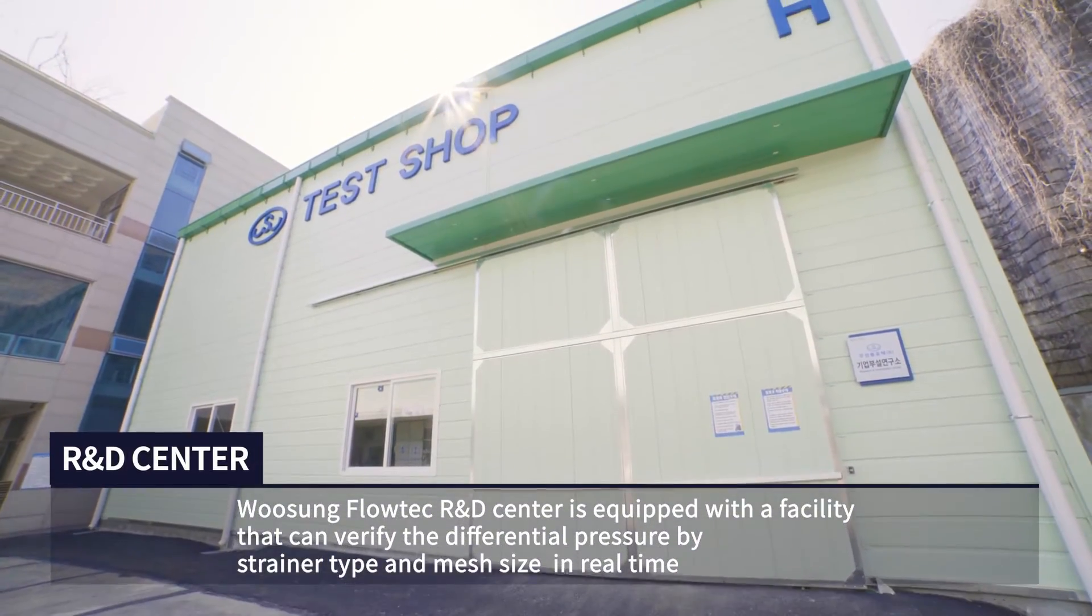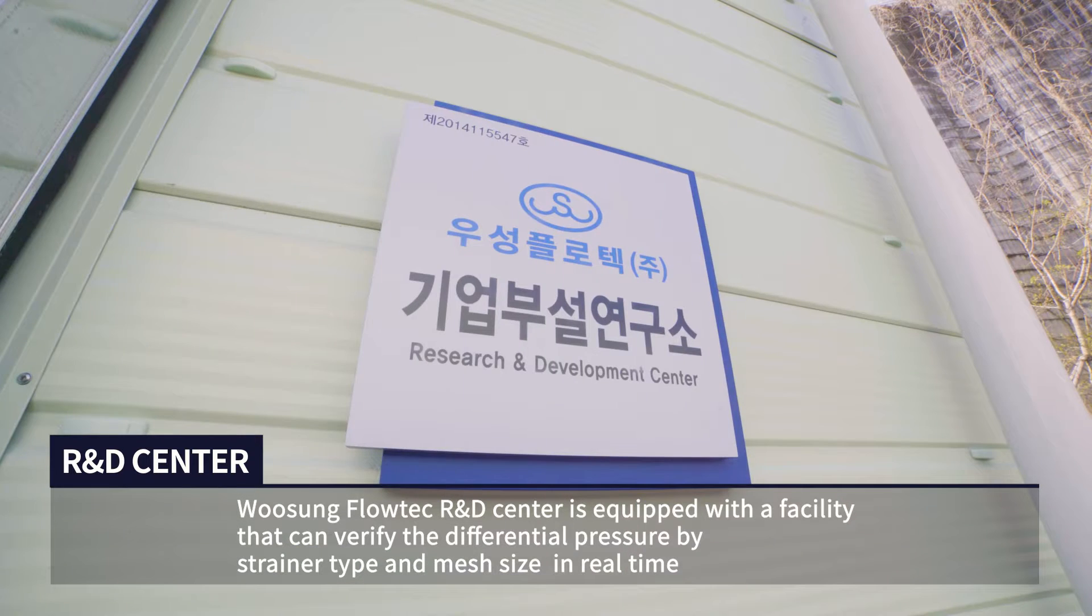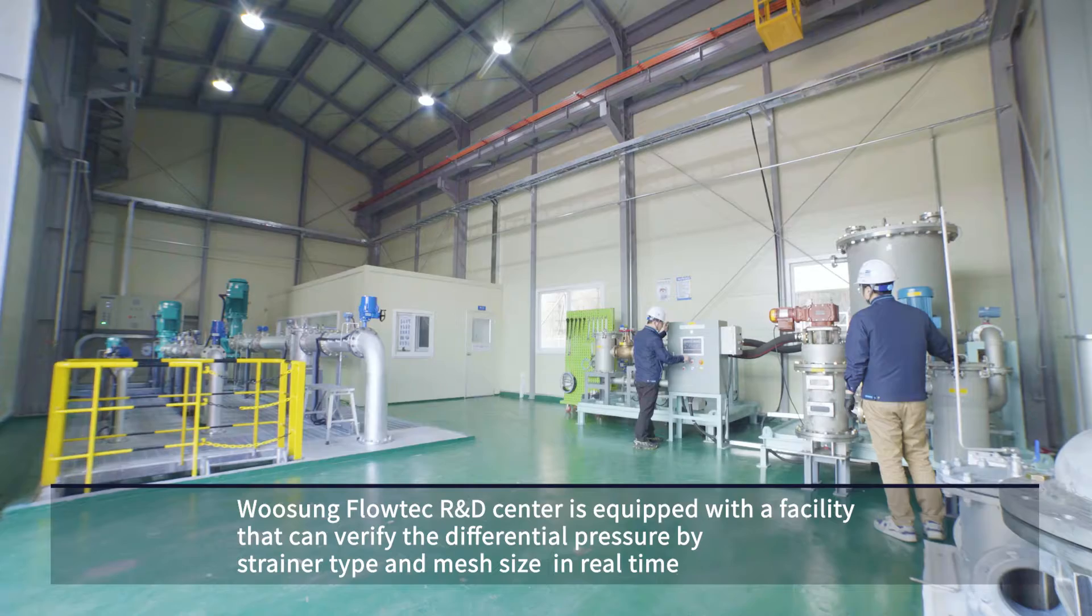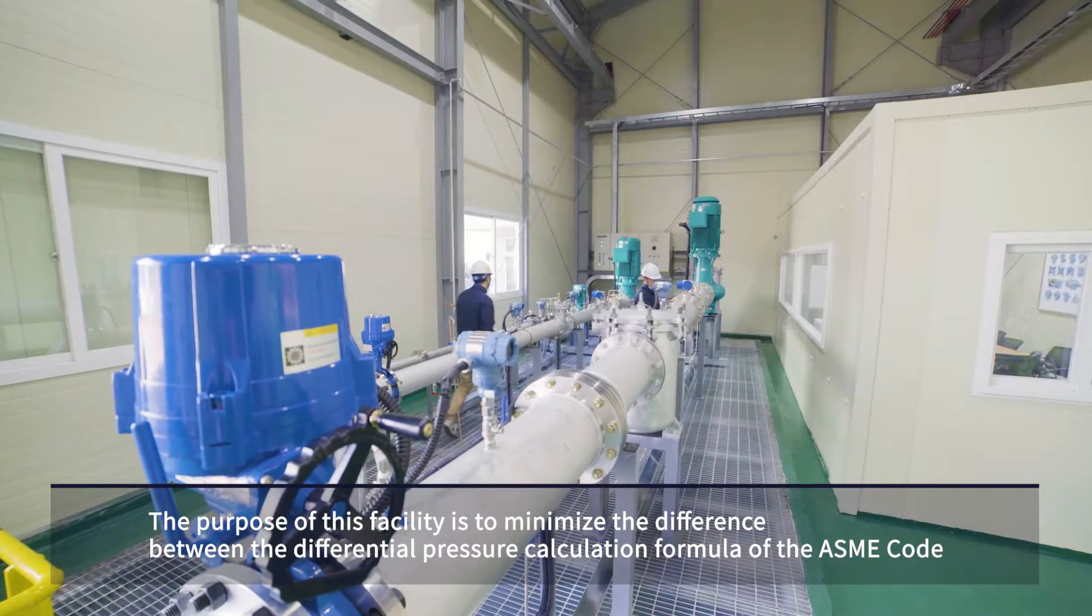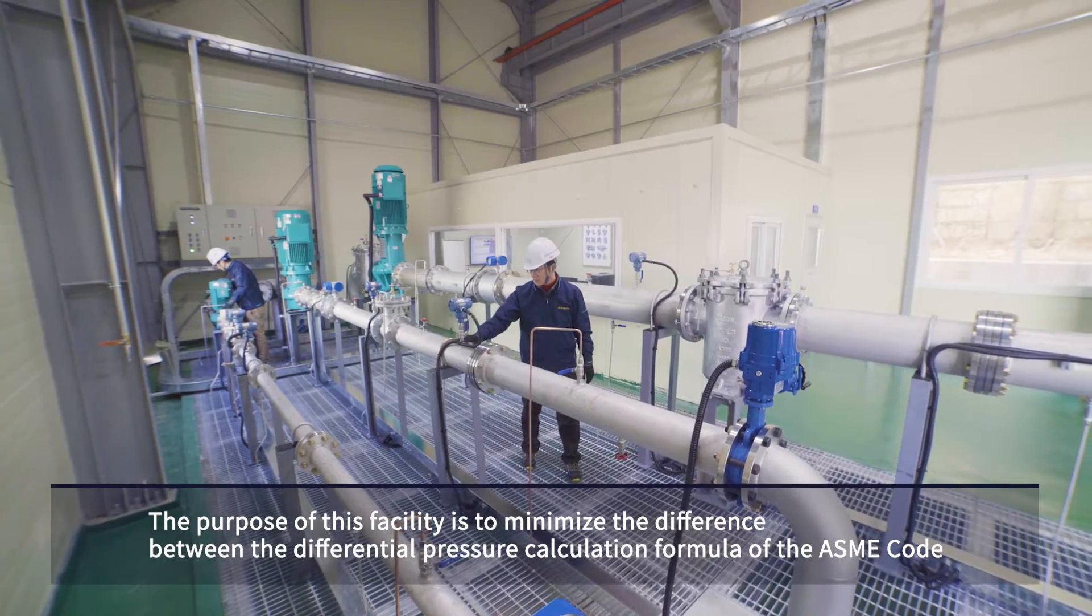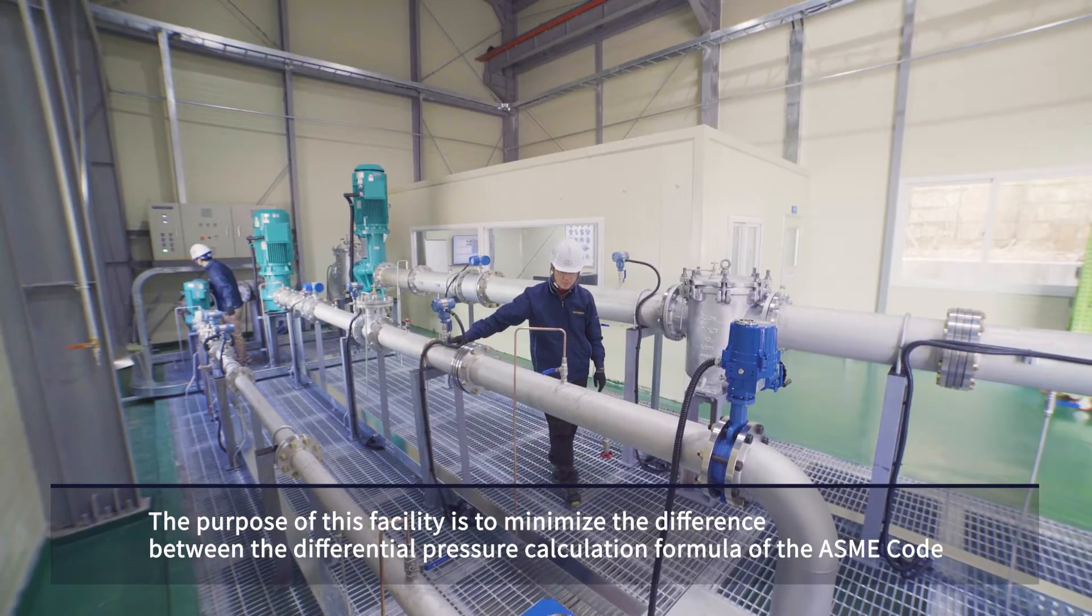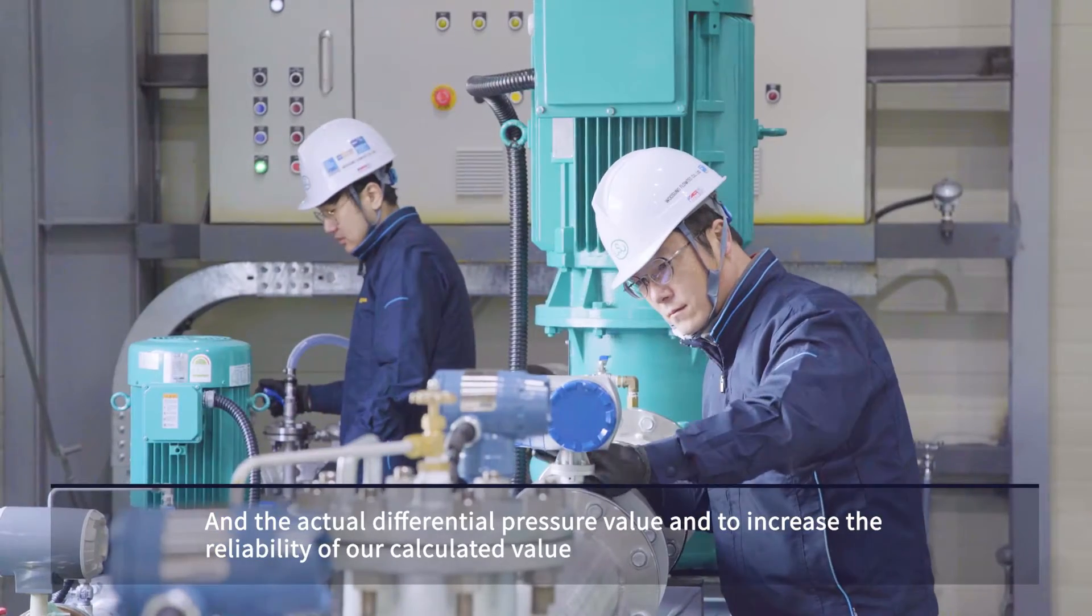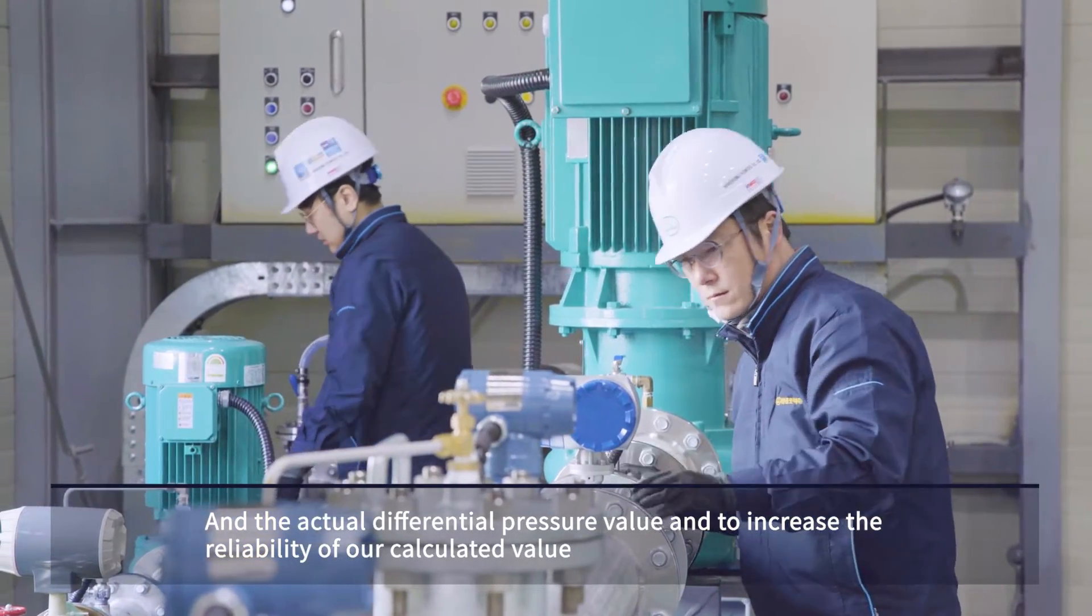Woosung Flowtec R&D Center is equipped with a facility that can verify the differential pressure by strainer type and mesh size in real time. The purpose of this facility is to minimize the difference between the differential pressure calculation formula of the ASME Code and the actual differential pressure value, and to increase the reliability of our calculated value.